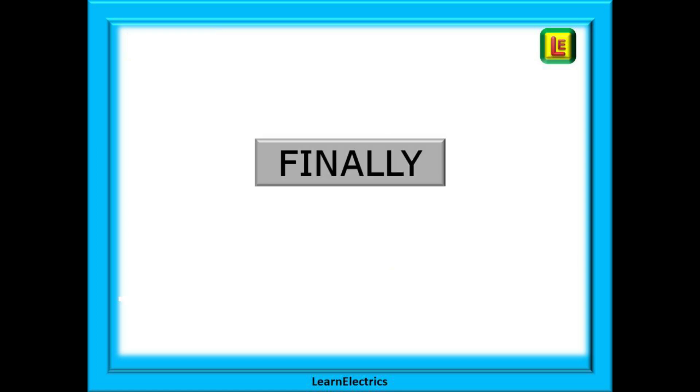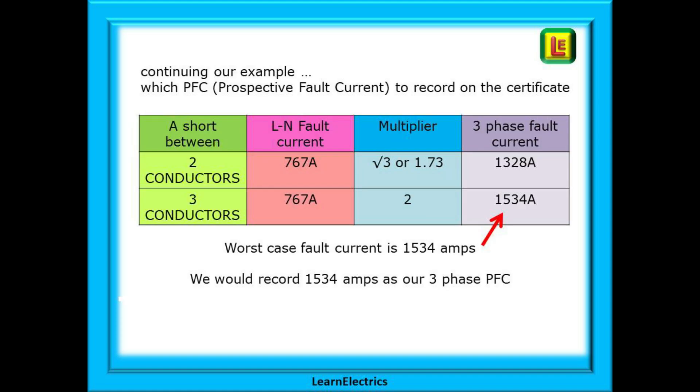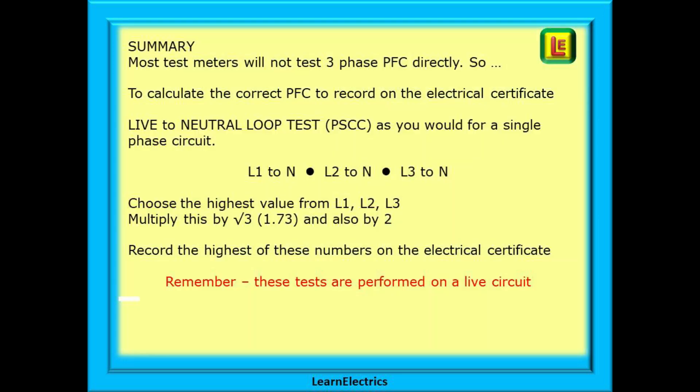Finally, which value are we to write on our electrical certificate? Look at this little table as we continue with our example. Which prospective fault current should we enter on the paperwork? It must always be the worst case values. If our installation can handle the worst case, then anything less than that should be OK too. Follow the table through to the rightmost column and you can see that we have two values of fault current: 1328 amps and 1534 amps. Here, we should enter 1534 amps as the three-phase prospective fault current.